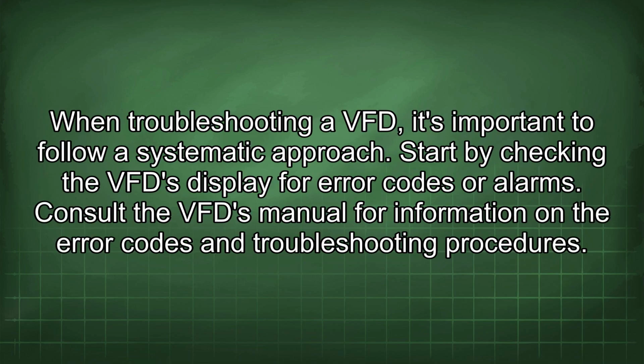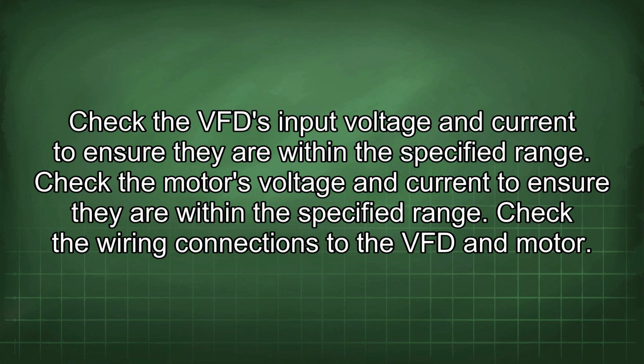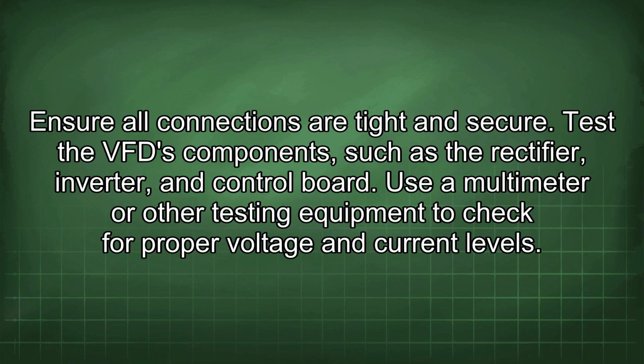When troubleshooting a VFD, it's important to follow a systematic approach. Start by checking the VFD display for error codes or alarms. Consult the VFD manual for information on the error codes and troubleshooting procedures. Check the VFD input voltage and current to ensure they are within the specified range. Check the motor's voltage and current to ensure they are within the specified range. Check the wiring connections to the VFD and motor. Ensure all connections are tight and secure.